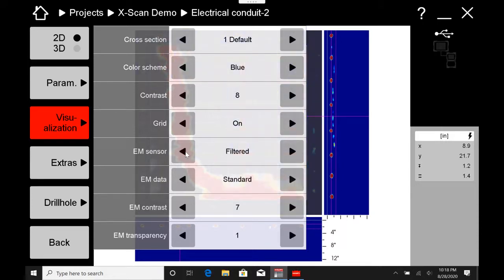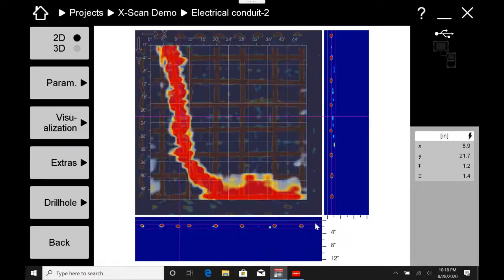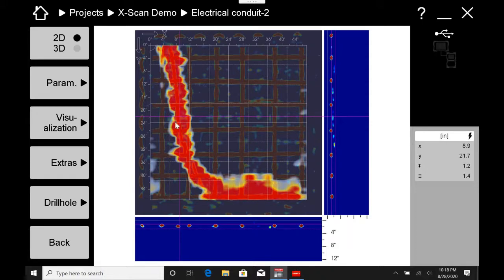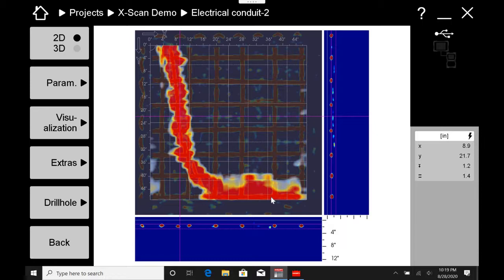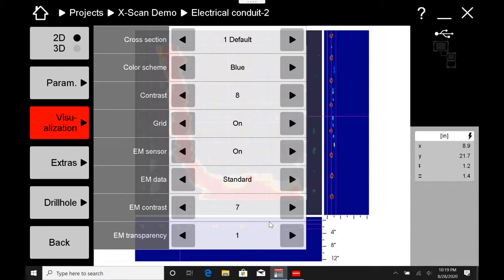So here's a scan. I'm going to turn this off in a second that has the EM sensor turned on. And when I use the EM sensor, you can toggle between filter mode or just normal mode. Or, of course, you can also turn it off. This is just simply view preferences. Filter basically will clean it up a little bit for you. But sometimes I like to just keep it turned on to see the full data. And let me show you what EM will look like. You can see here that a conduit of some sort is obviously in the slab. And this red color here is indicating where that conduit is pulling live electricity. And let me make a quick note. I've made a quick note about this before in other videos. But if you are using the EM sensor, please remember that it's simply a guide. It's not perfectly accurate. It's just trying to pull as much electromagnetic activity that it can find. And sometimes that's interfered with electrical boxes nearby or even cell phones or things like that in the area. So just know that this isn't always 100% perfect, but it certainly could help you and be a guide for you. And these just simply let you change the contrast for your electromagnetic activity sensor that you saw or the transparency, whether or not you want to see that more transparent or not so you can see the other parts of your radar scan. So that's what the EM sensor looks like. And if that's something that you need, that's how you adjust some of the settings on the view.